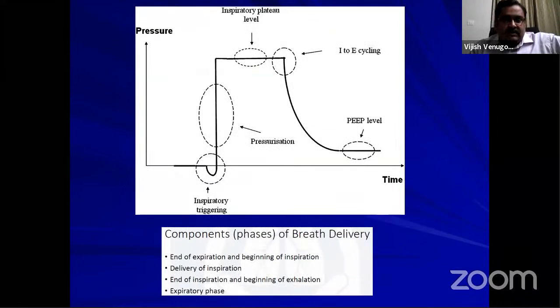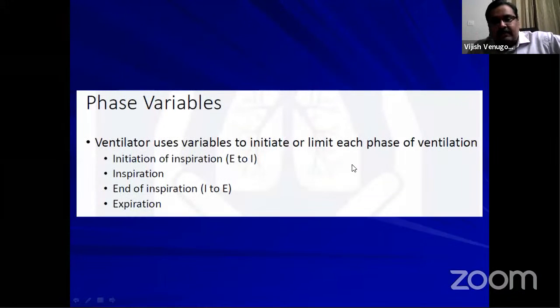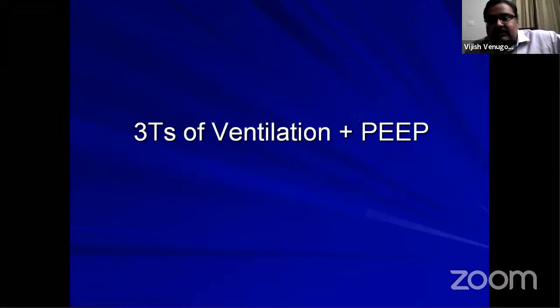Now, if you look at this pressure tracing, there are different components of the breath. If you look here, the first part is the end of expiration to the beginning of inspiration. You can see there is something called a triggering part here. Then there is delivery of inspiration, followed by end of inspiration and beginning of exhalation. And the expiratory phase is the one that is showing the PEEP level there. So there are 4 different phases. Each phase, the ventilator will use variables to initiate or limit. So these are called phase variables. This can be remembered as the 3 T's of ventilation along with PEEP. So the first 3 are T's and the last one is PEEP, or the baseline variable.